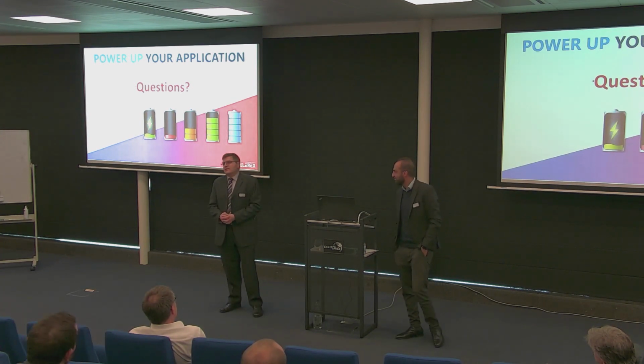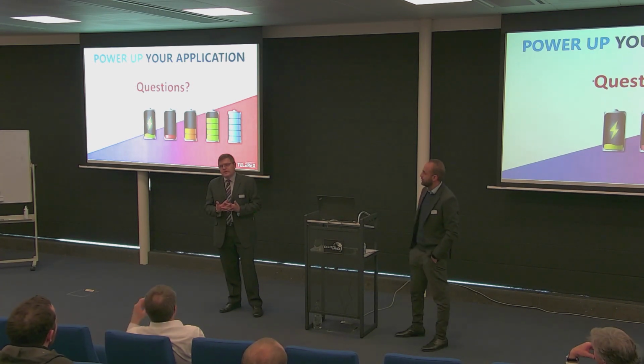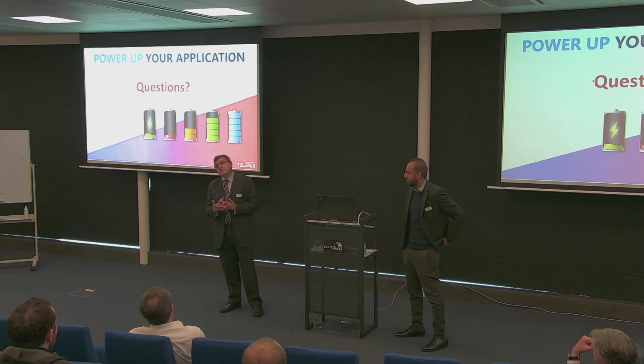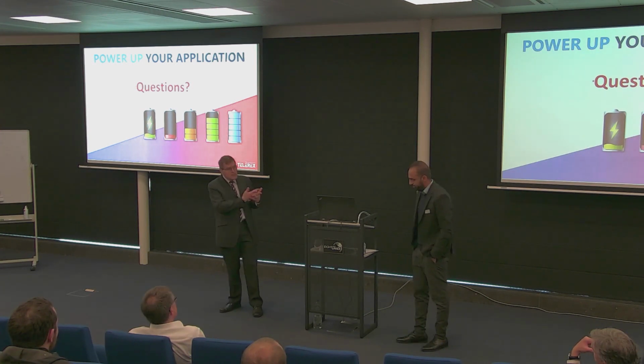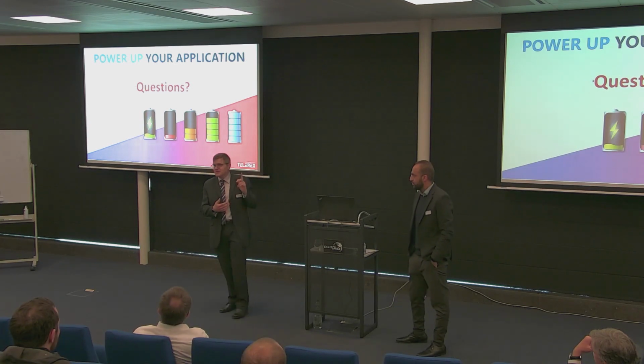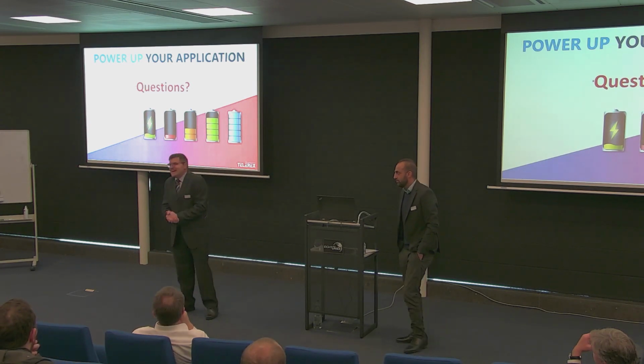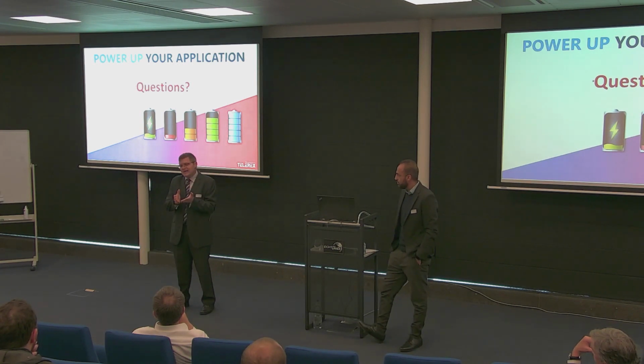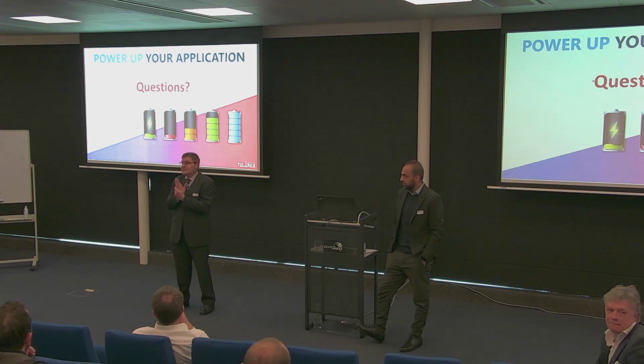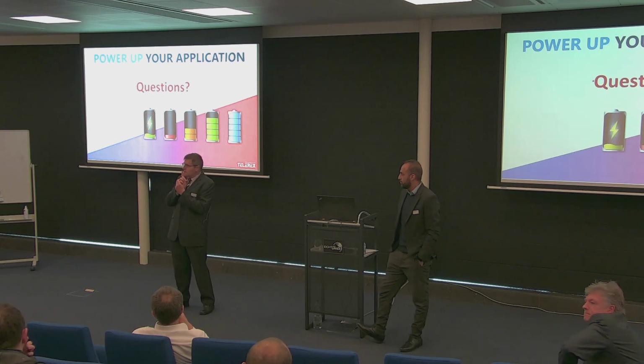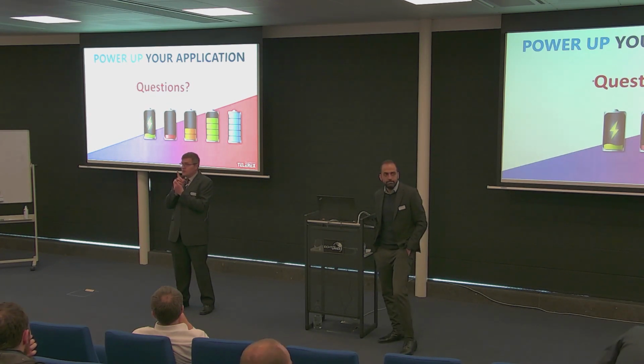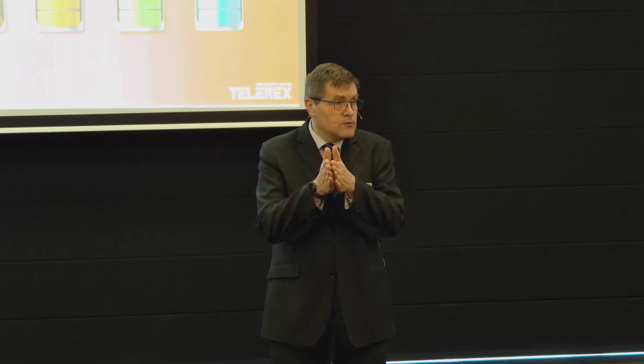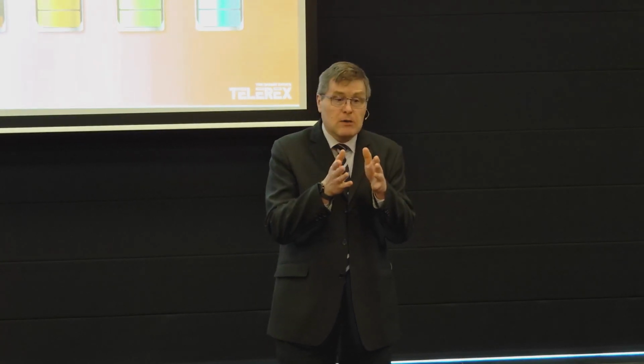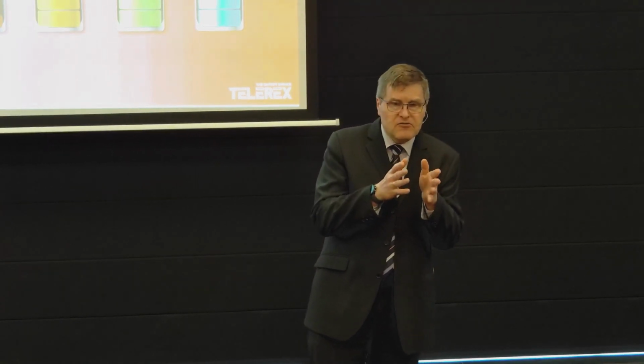So, there are standards, for example, the IEC 61000-3-6, which is emission in industry. This is not a standard which was listed in the other presentation, because I was looking for that. This is the maximum emission limit for industrial application, which is 8%. But this is the maximum that the utility has to guarantee. So that means that as a utility, I have to respect this, so I need to take some safety margin. So I will maybe consider 7 or 7.5 or 6.5%.